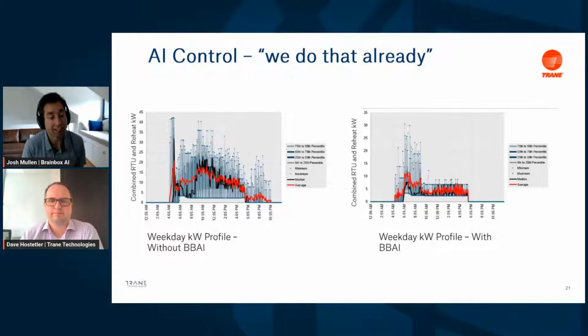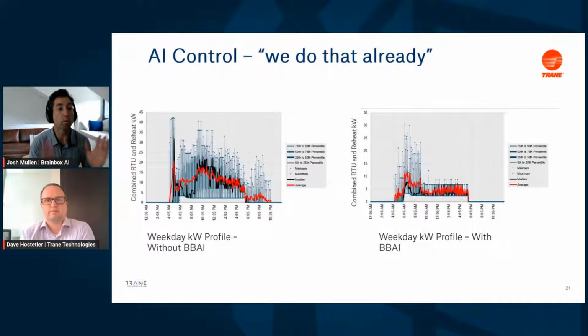We often hear, 'but I already have optimum start, or I already have static pressure reset and supply air temperature reset.' And that's true. We go into a lot of buildings that already have this, and what we're finding is generally either it hasn't been commissioned properly, or they're missing some input necessary to do true optimization.